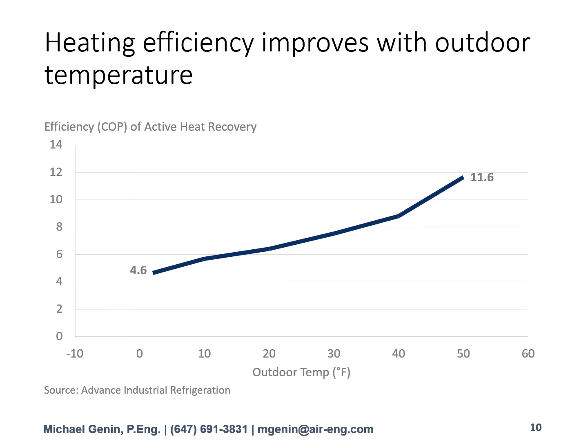And the reason for that is, if we think of, let's say, a conventional chilled water system or a chiller, when you talk about part load efficiency of the chiller, or NPLV, the efficiency of the chiller gets better when the ambient condition or your condenser water cooling tower relief occurs, when you have part load on the compressor and part lift given by cooler ambient conditions.